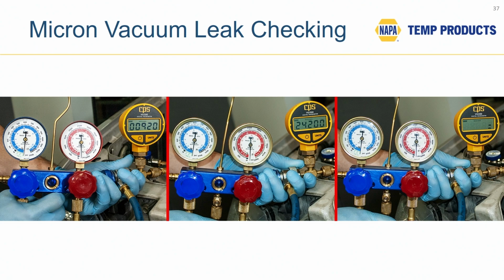If you're just looking at a conventional gauge, it looks like it still has excellent vacuum. Over here on the right-hand side, the blue gauge still appears to indicate excellent vacuum, but the micron vacuum gauge, which won't start to read until you get to about 28 and a half inches of vacuum, has actually stopped reading altogether. The takeaway is that using a micron vacuum gauge is a much more accurate way of confirming and validating that the vacuum pump is getting down to the deep vacuum that you need to remove all moisture from the system, especially in hot, humid areas where you've got very high humidity.